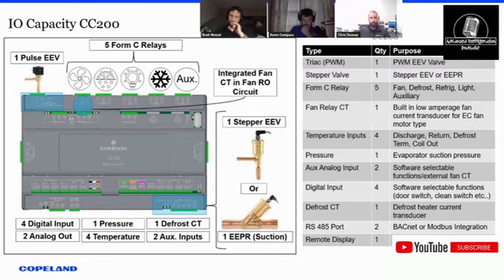I thought I'd give you a little walk around the hardware and then go over some specific features on the hardware before we jump to a demo. Kevin was asking about that external solid state relay earlier. On the top left, we have a triac built into the board that does the switching for the pulse valve. It has a configurable period of control. It defaults to 6 seconds, which is kind of your standard right now. So that's where we handle that pulse valve, top left on that connector.